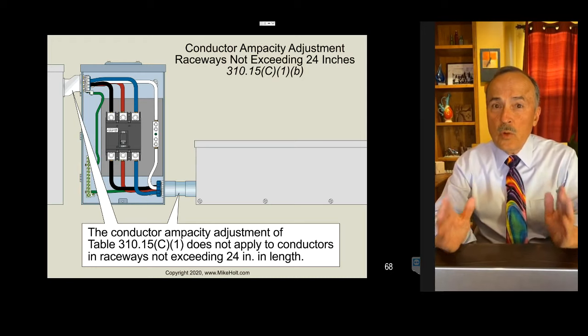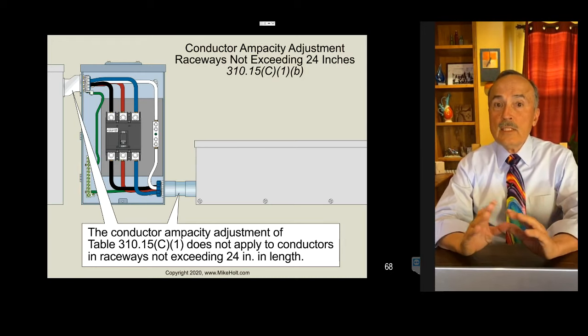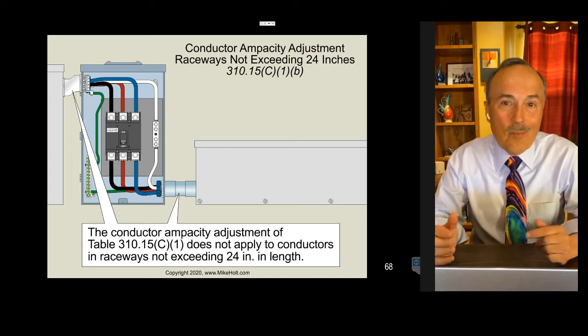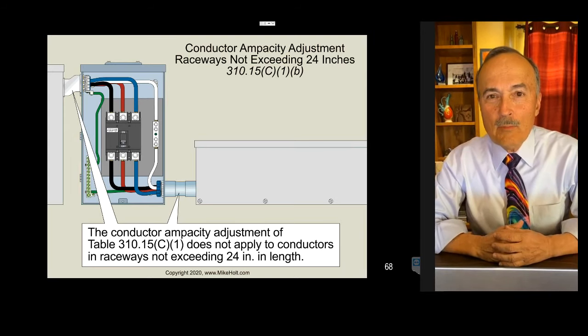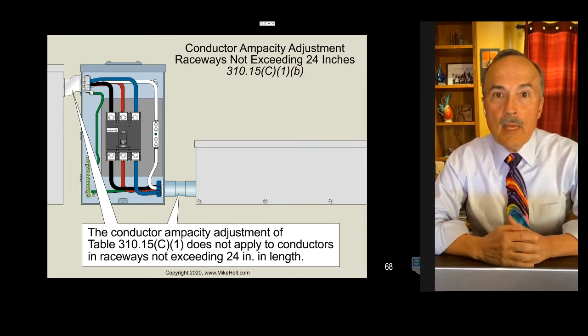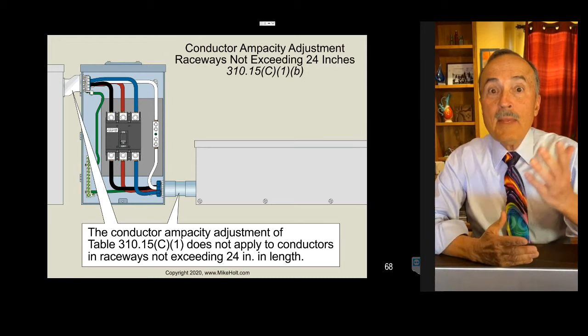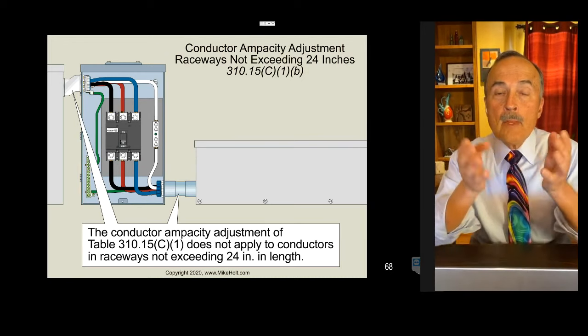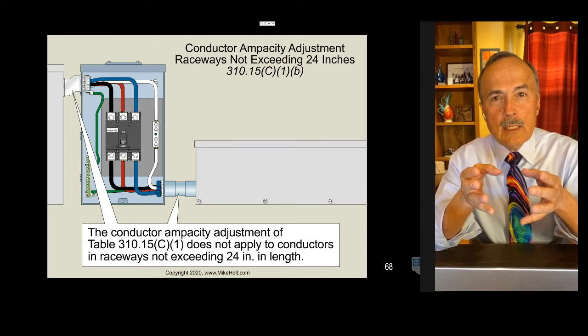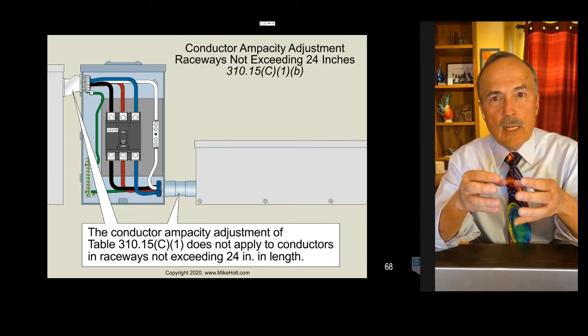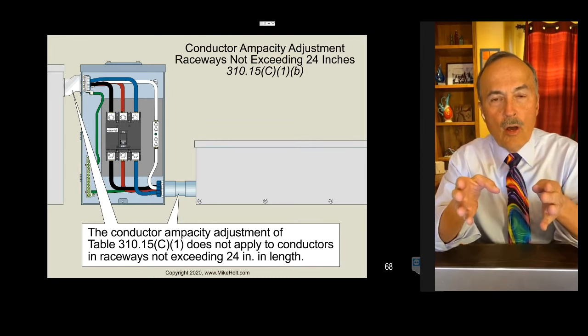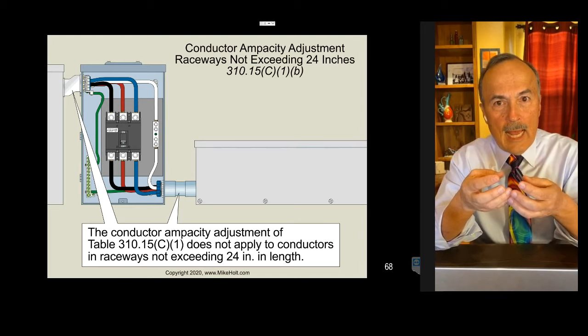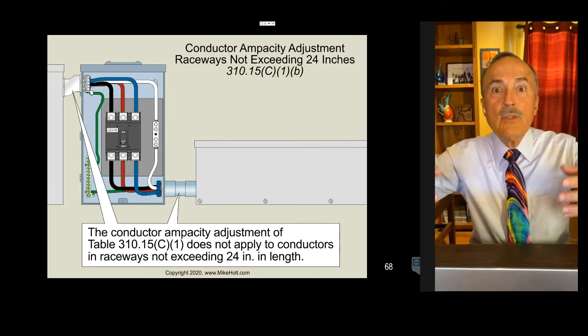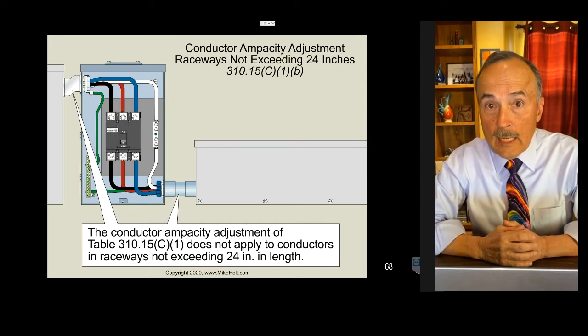Now, this adjustment does not apply to a raceway if you're not going more than 24 inches. Then this adjustment factor does not apply. So if you're in a raceway, the code calls it a nipple, 24 inches or less, then this adjustment doesn't apply. Why not? I don't know. Where did 24 inches come from? 2 feet, it's a round number. Hey, maybe in another country they might use a meter because that's a convenient number.